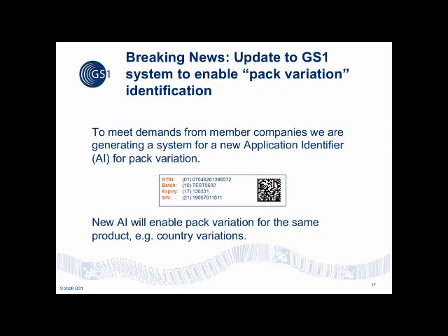Now, what we can see here on the screen is a standard GS1 data matrix with a GTIN identified. If you look just after it says GTIN in the brackets, there is a 01. That is called the application identifier. The application identifier 01 identifies a GTIN. The next one down, the 10, identifies a batch number, which is in this case test 5632. The next down, number 17, is the application identifier for an expiry date. And then 21, the application identifier for a serial number.